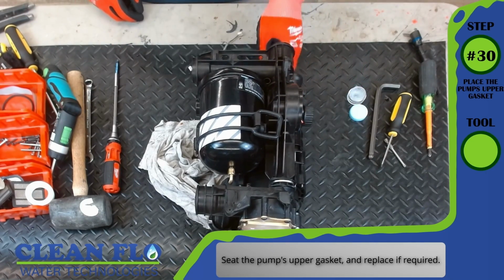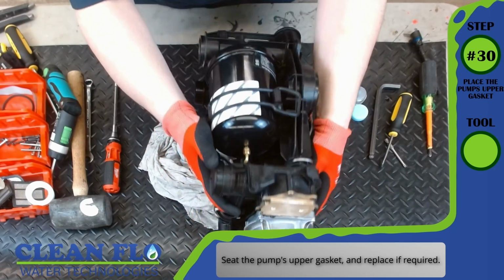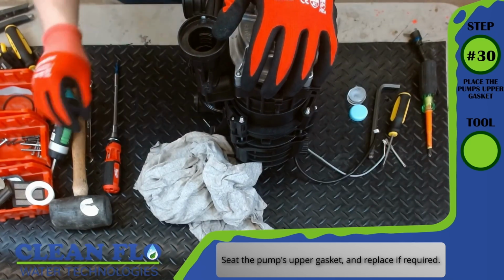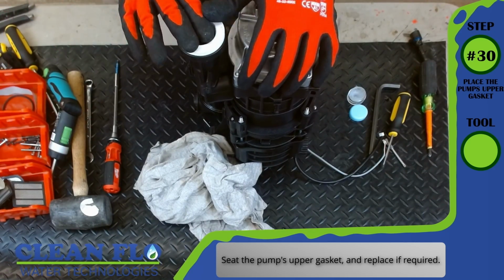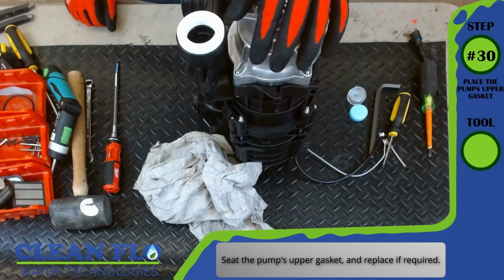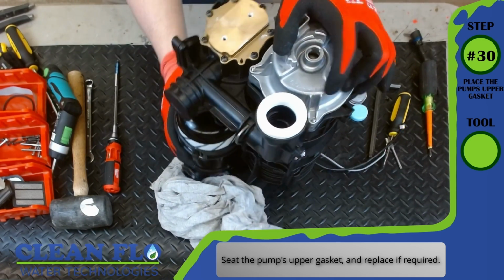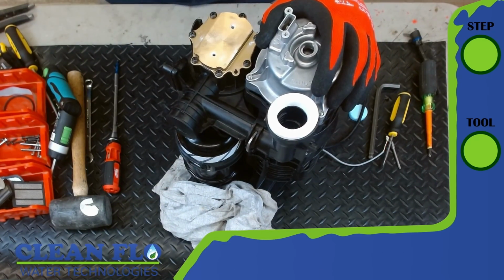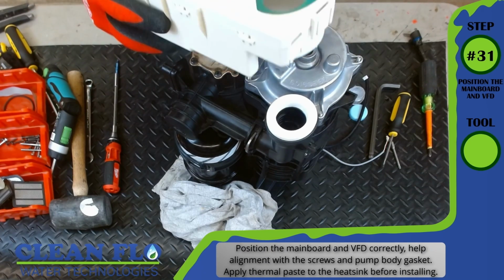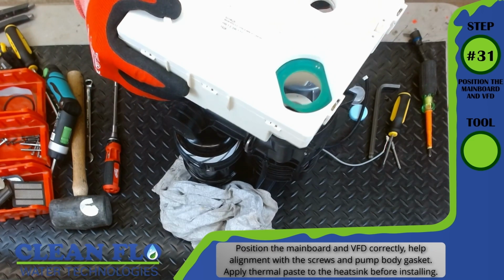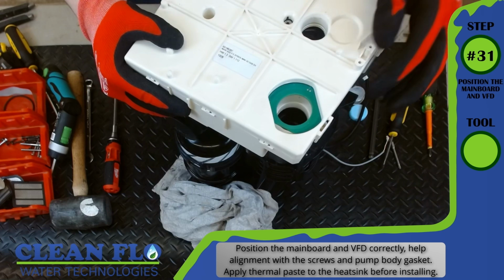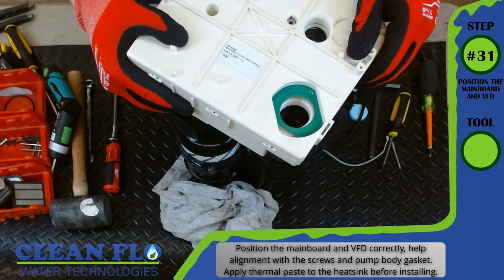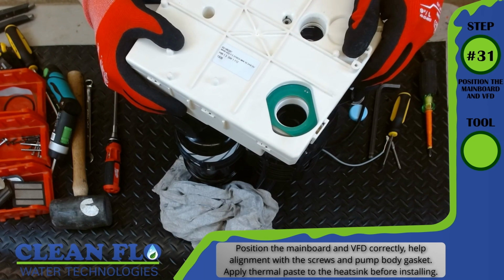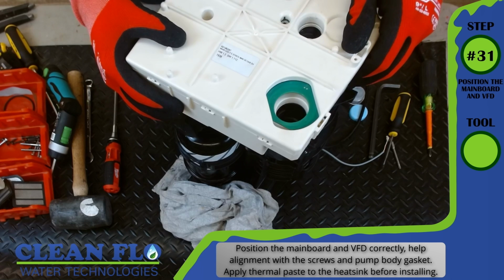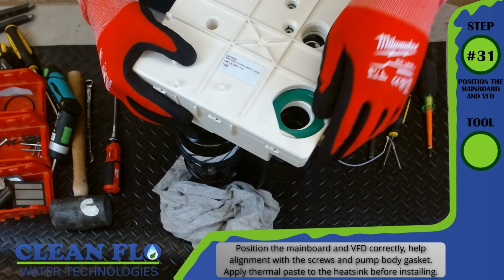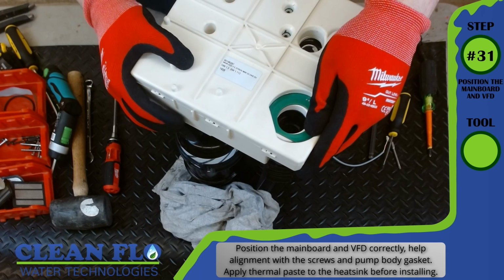Step number 30, place the pump upper gasket. No tool required. Seat the pump's upper gasket and replace if required. Step 31, position the main board and VFD. No tool required. Position the main board and variable frequency drive correctly. Help alignment with the screws and the pump body gasket. Apply thermal paste to the heatsink before installing.